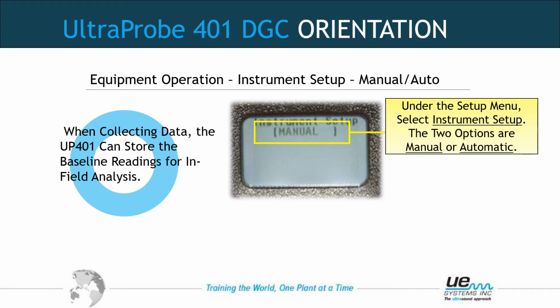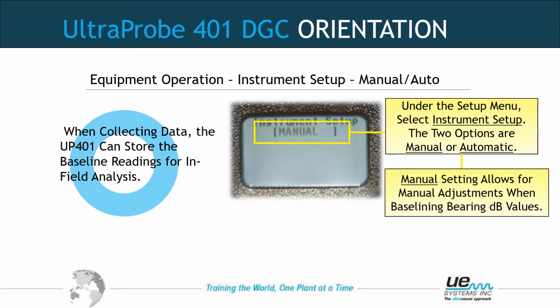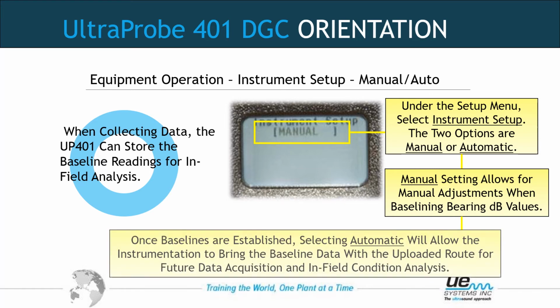But once everything is baselined, we want to come to instrument setup and change this to automatic. By changing to automatic, it allows the unit to pull all the baseline information over and set the unit to the same frequency, sensitivity, and show you the readings that we're taking during the baseline. This does this per test point. So during baselining, we want the instrument in manual. For every other route after baseline, we want the instrument set up in automatic.